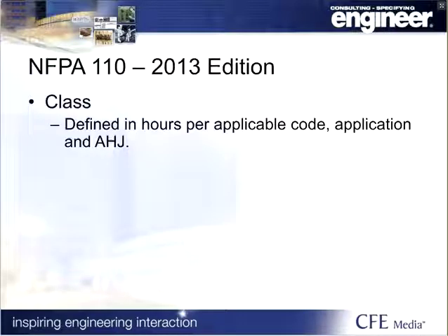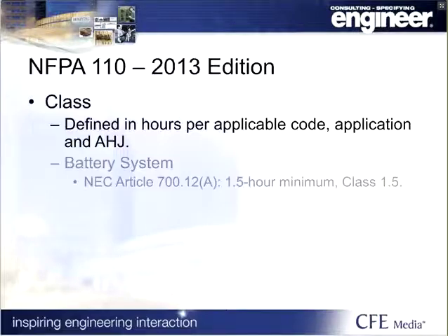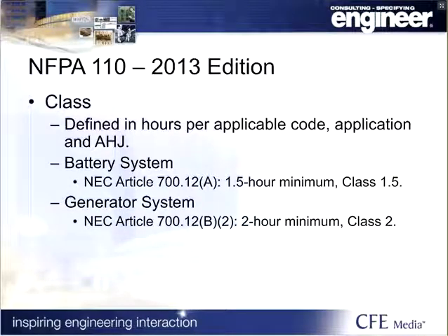NFPA 110 Chapter 4.2 defines the system class in hours. Since NFPA 110 is only the standard that sets up the criteria, the relevant class value is identified by the applicable code, application, or AHJ. For example, a battery-based system would require a minimum runtime of 1.5 hours per NEC Article 700.12(A). The class would be 1.5 in this case. NEC Article 700.12(B)(2) requires a generator to have enough fuel to operate for 2 hours minimum, which would make this a Class 2 system.